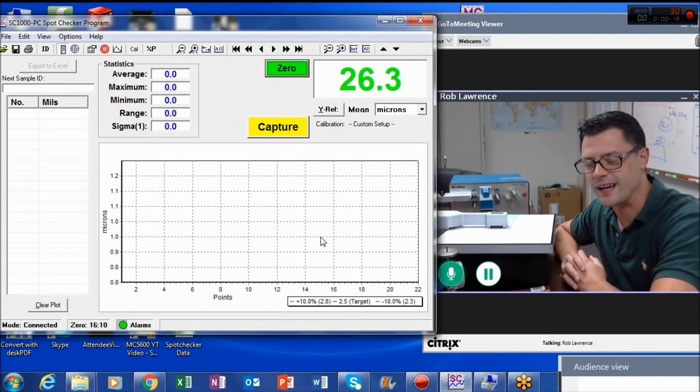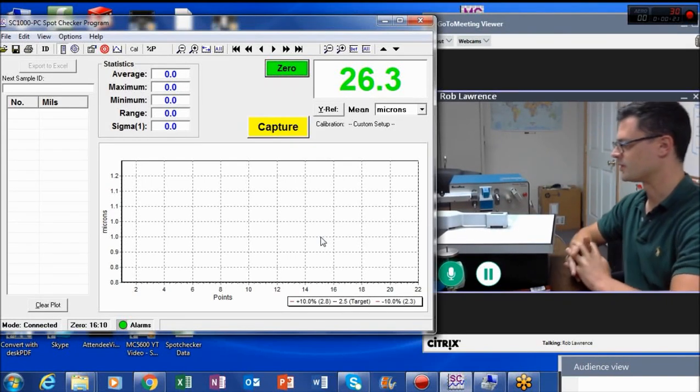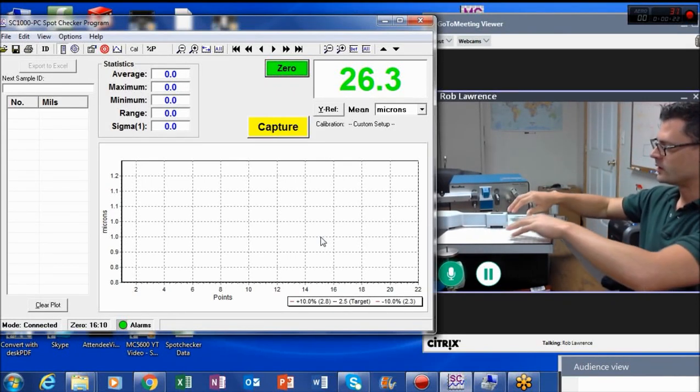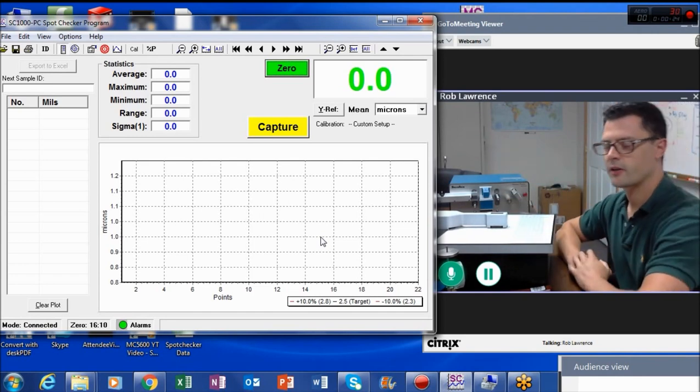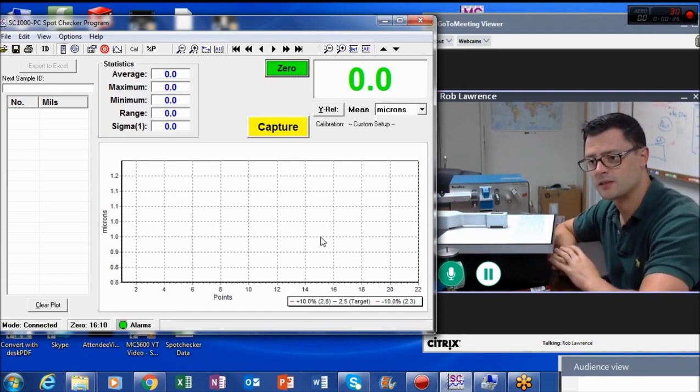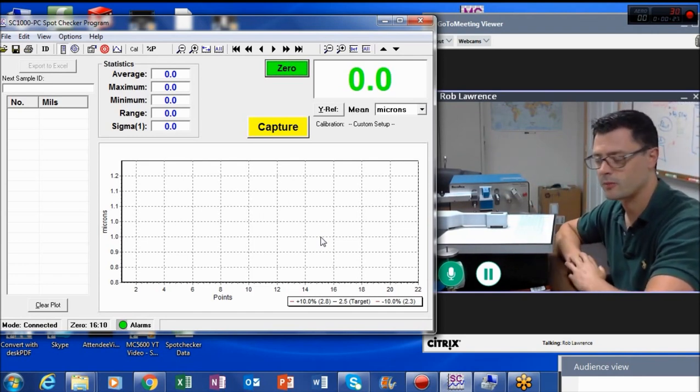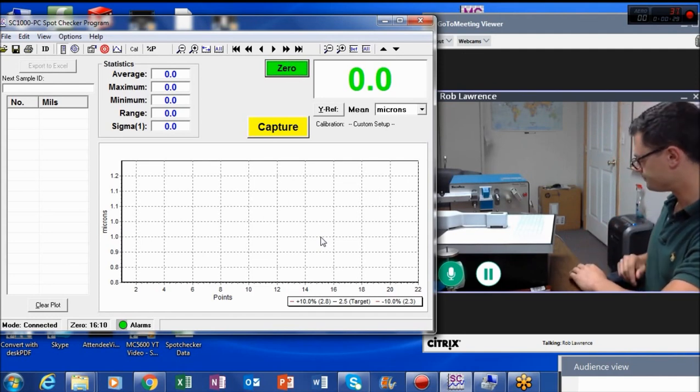I want to introduce you to the SC-1000 Spot Checker from Solvetech. This is a non-contacting micrometer. It's capacitance-based, based on our proprietary capacitance technology.